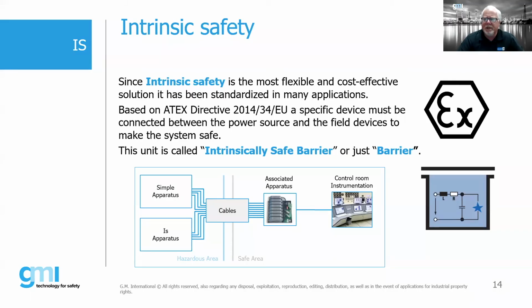So focusing our attention on intrinsic safety, what are some of the components of what we talk about? It is one of the most flexible and cost-effective solutions. And the good thing is that if you're familiar with intrinsic safety installations, the concepts for the most part, worldwide, the standards are all very similar, meaning that if you've done an intrinsically safe installation design, say, to comply with the ATEX directive, the same requirements related in the EN standards are very similar to what you would find within the CEC in Canada or the NEC in the US or other world standards. Because intrinsically safe is a universally adopted and accepted protection concept.